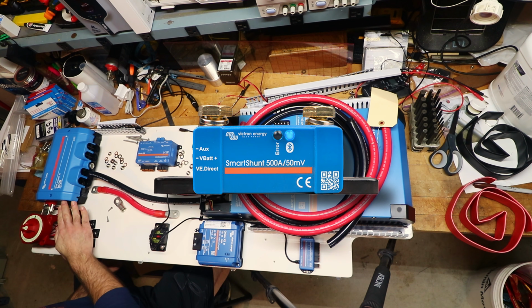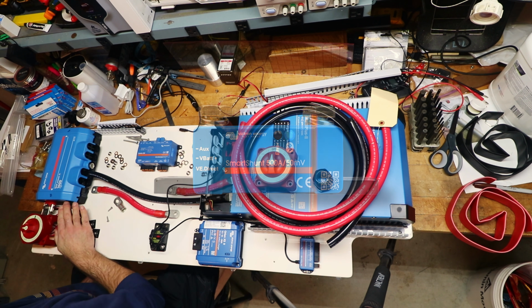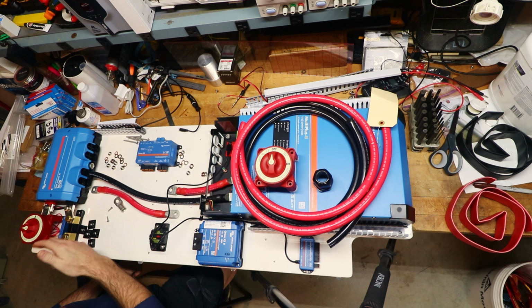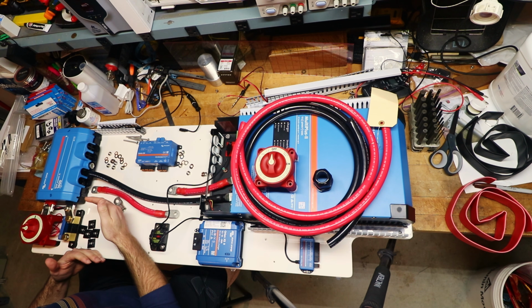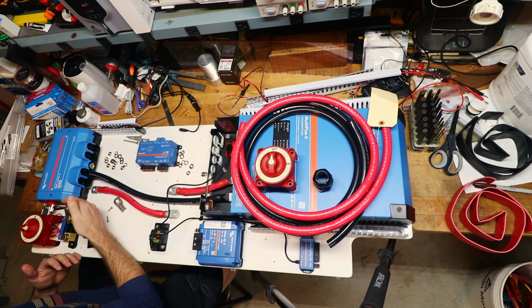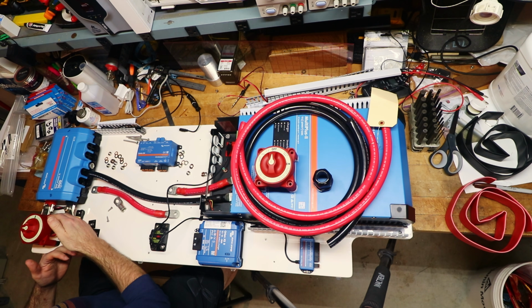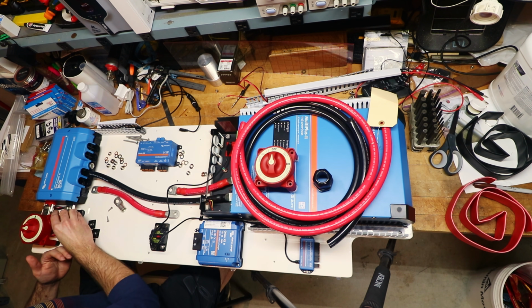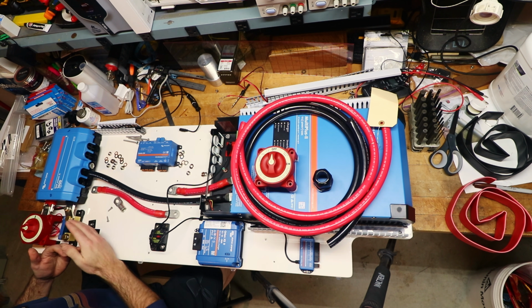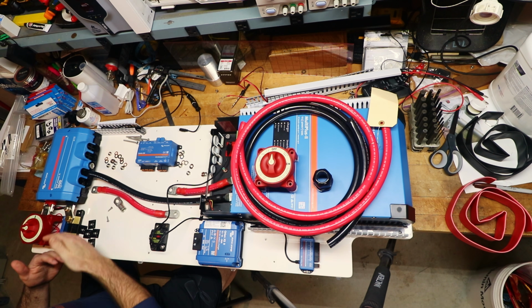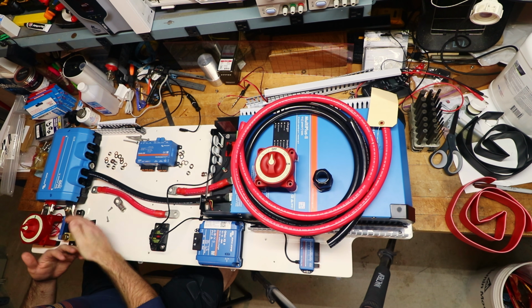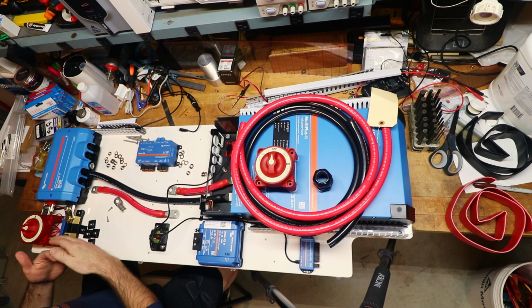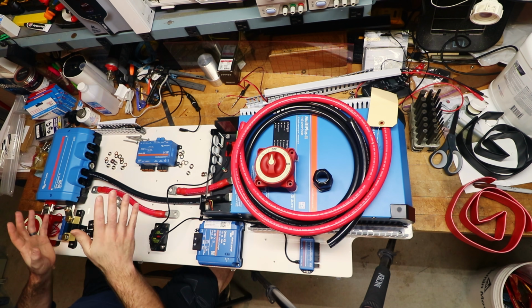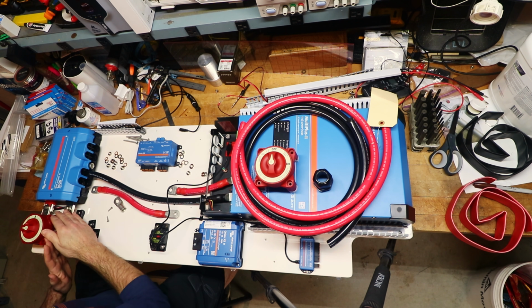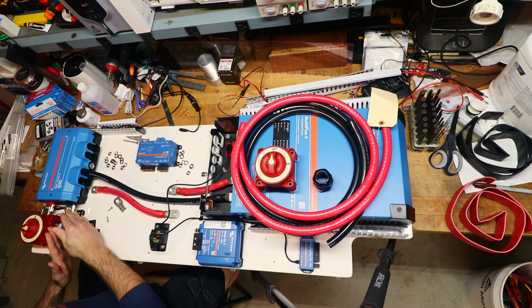This one specifically can read up to 500 amps - you can get it in different ranges. Now, the closer you match that max number to your realistic maximum, the better resolution you get in the current measurement. If you put a 1000 amp smart shunt in a system where you're never drawing over 50 amps, for example, you're going to lose some of the resolution of your measurement, and over time it may become a little bit less accurate when it reads the battery voltage and charge and all that kind of stuff. So you kind of want to match it to your system as best you can.